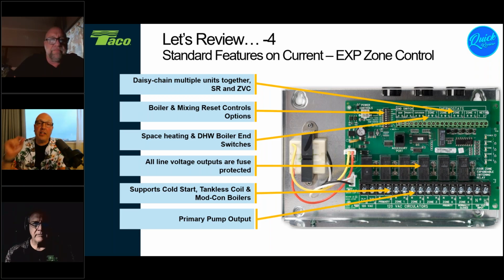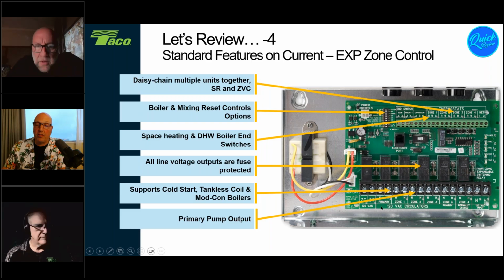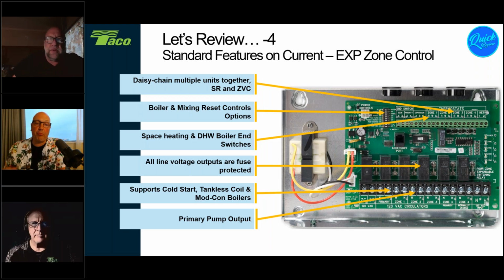And on the expansion, the EXP boards, we had on this switching relay, for example, you'll see an extra circulator relay built in that we would call our primary pump. So for some of those ModCon boilers that had to have a separate circulator that wasn't built in, but you had to make sure it was controlled properly, we had that primary terminal here. So this is showing a 4-zone system where I can actually run 5 pumps.